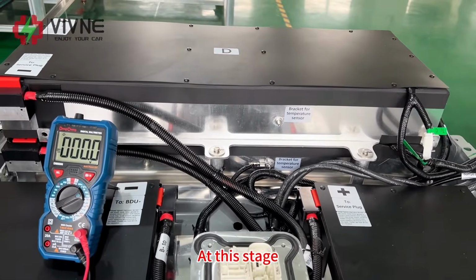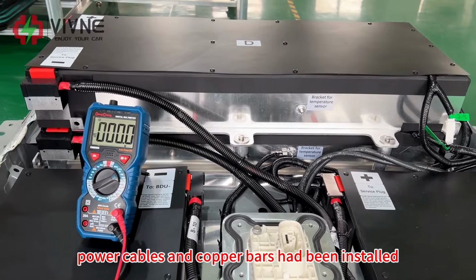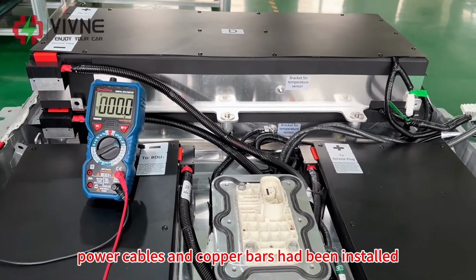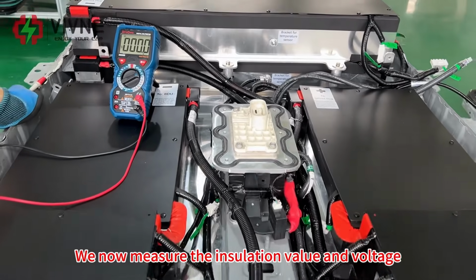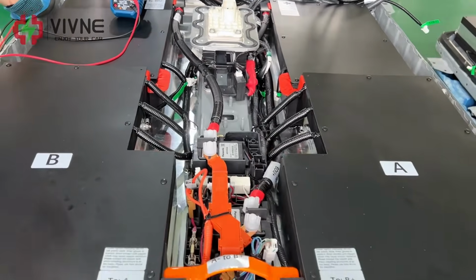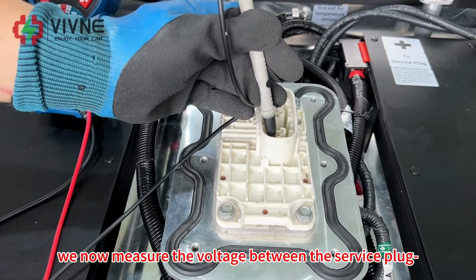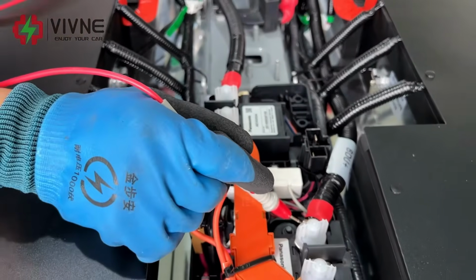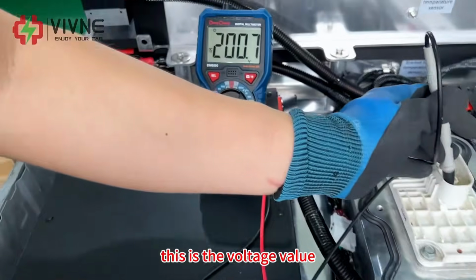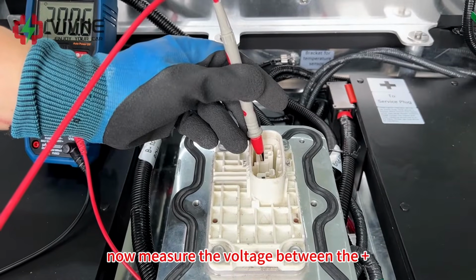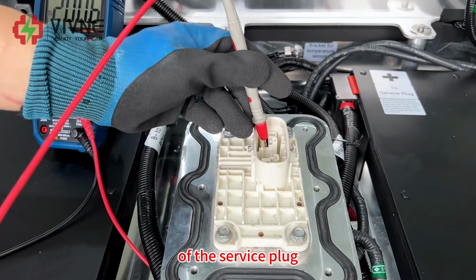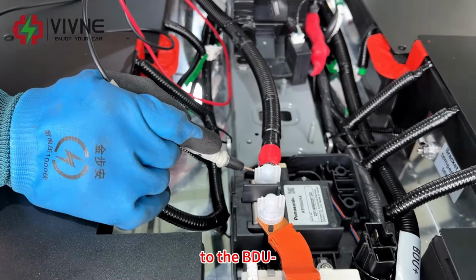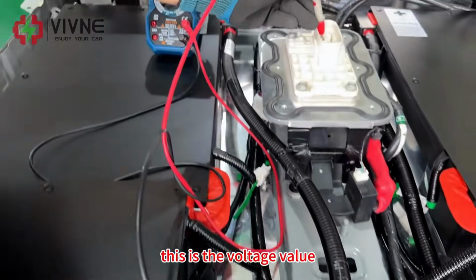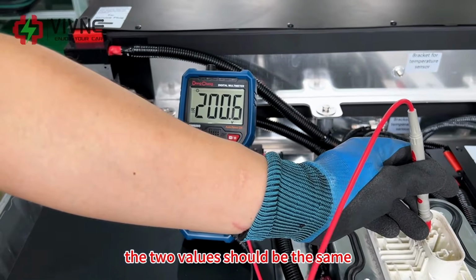At this stage, all the power cables and copper bars had been installed. We now measure the insulation value and voltage. We now measure the voltage between the service plug negative to the BDU positive. This is the voltage value. Now measure the voltage between the positive of the service plug to the BDU negative. This is the voltage value. The two values should be the same.